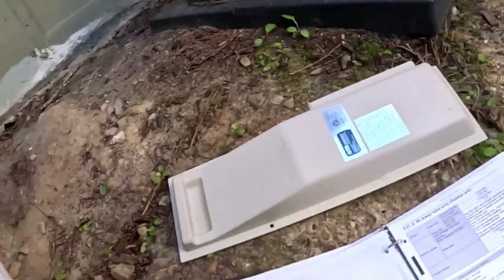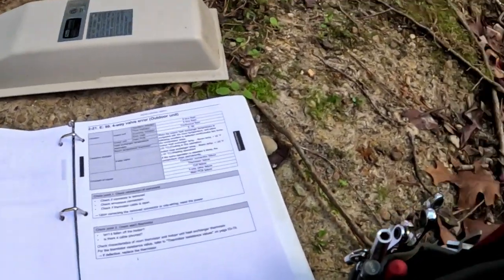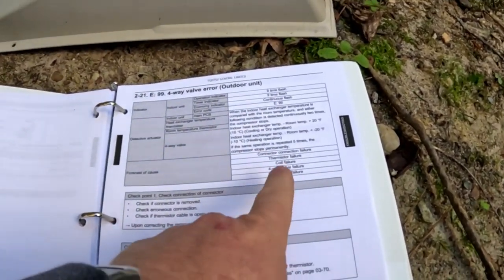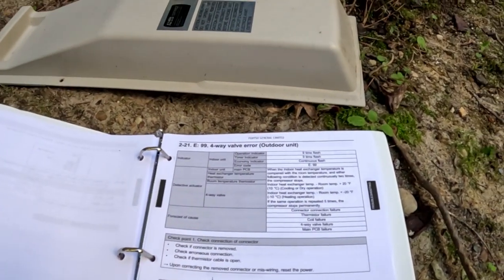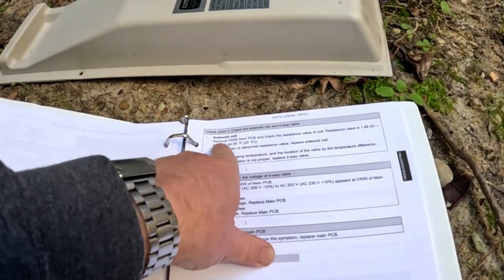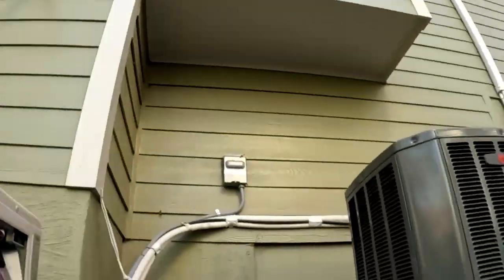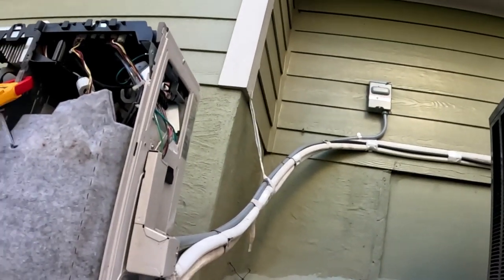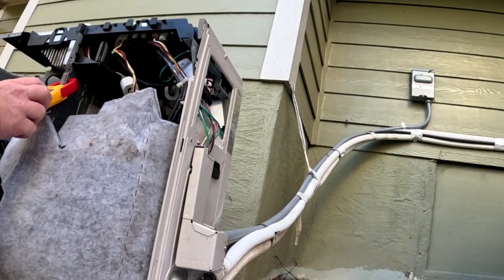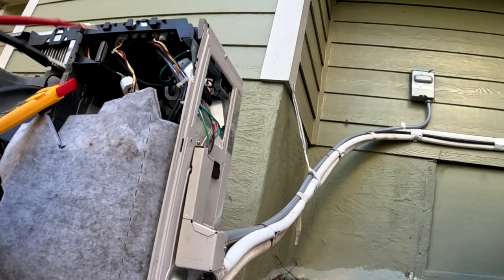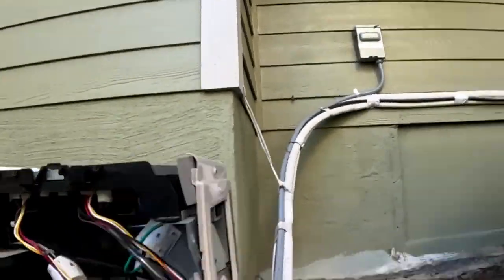So that's kind of odd, unless it just relays all the faults back to the indoor unit. But I'm not seeing anything in here or anything on the diagram that was in this book that shows a light. So first thing it tells you when you go to troubleshoot this is check the coil. We're gonna ohm that coil out, 1.8 to 2.2, somewhere in there. So we'll see how that ohms out as far as our solenoid coil, which is right here.